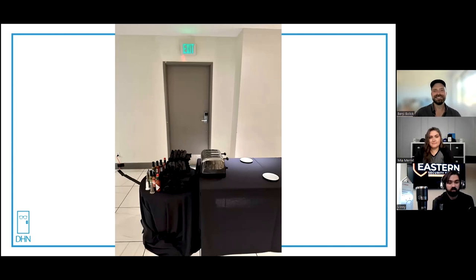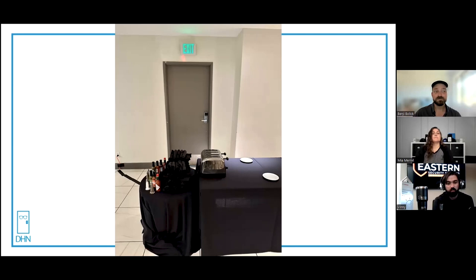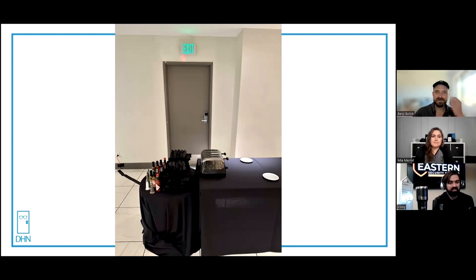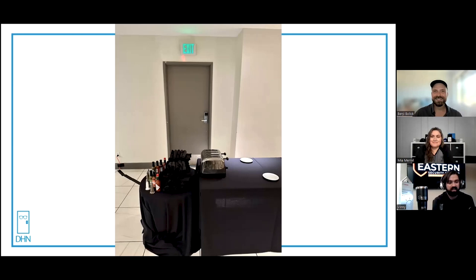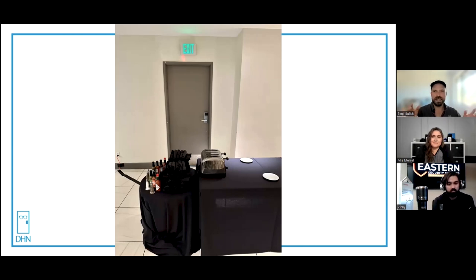But again, you know, the sprinkler goes off, fire alarm goes off, I mean you're sitting right in there, that's the direction you're going to go and you could potentially be running right into the fire. So that has to be, even if not for the card reader there, it's just a bad plan. Yeah, I mean there is code set up to where the path of egress can't go through like a hazardous environment.